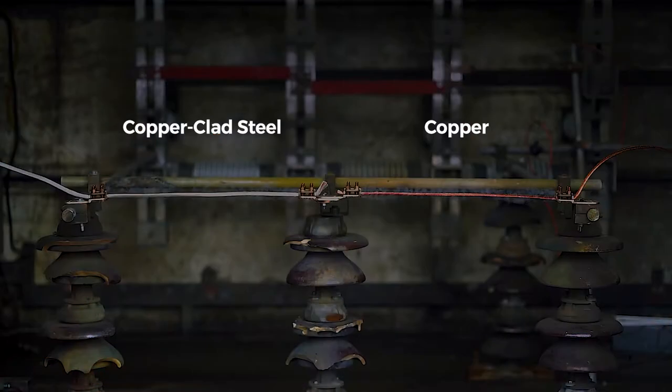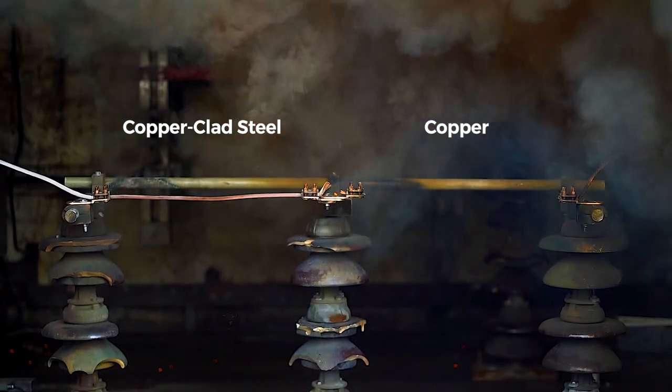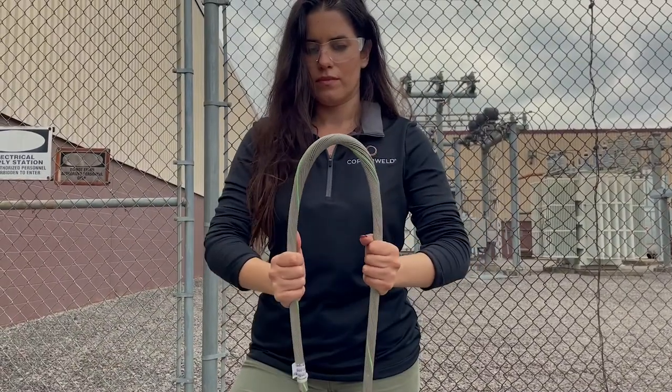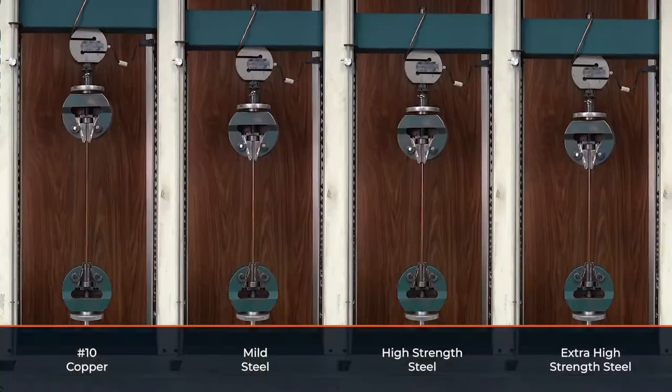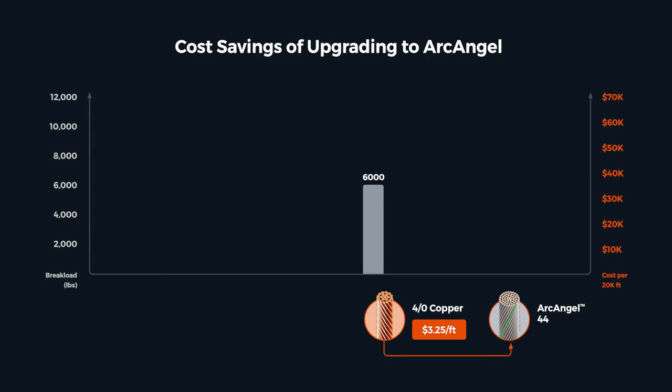After all our testing and development, we discovered that when copper-clad steel — CCS — is optimized for short circuit performance, flexibility, and corrosion resistance, it turns out it's also strong. Really strong. For example, a copper four-aught conductor has a break load of about 6,000 pounds. ArcAngel 44, that carries a little more current than a four-aught, has a break load of about 12,000 pounds.